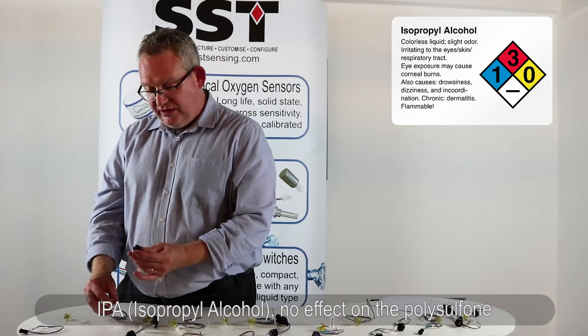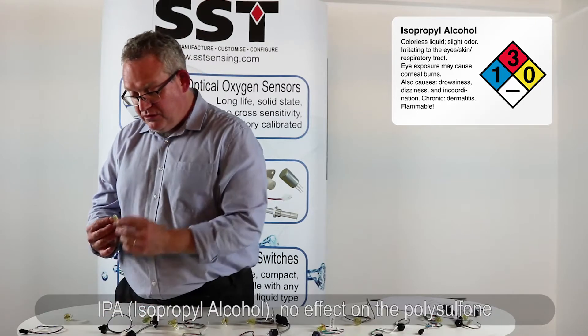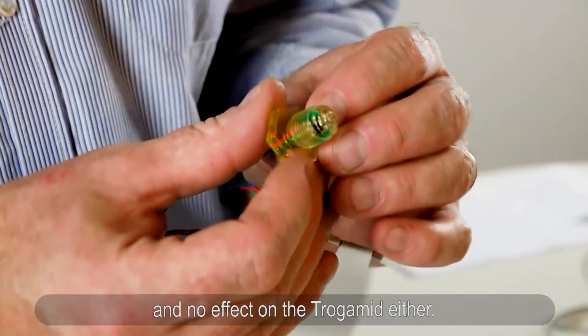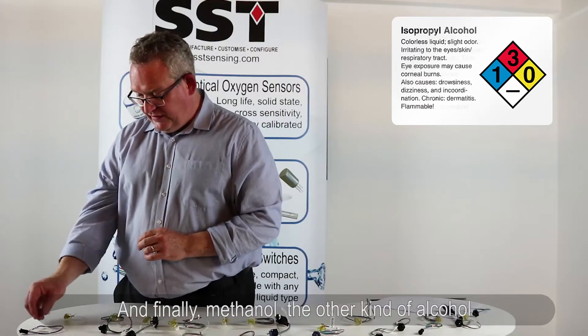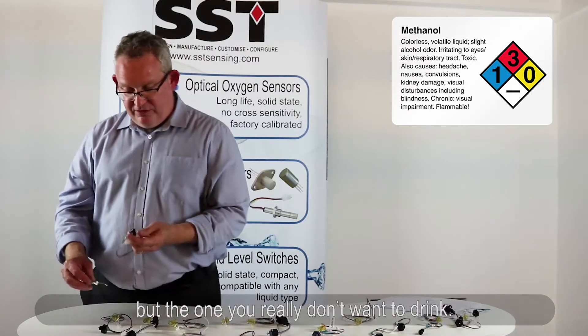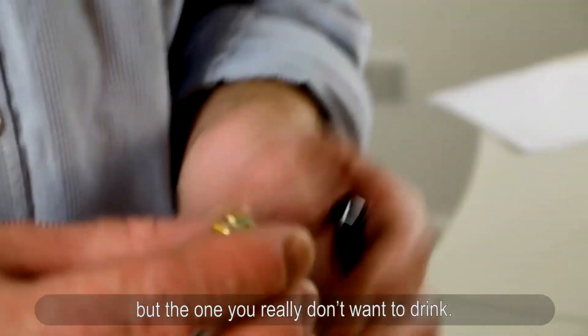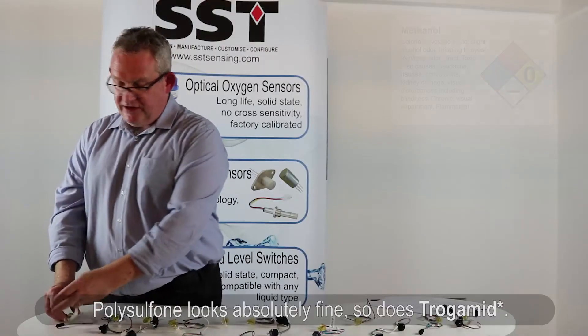IPA — isopropyl alcohol — no effect on the polysulfone and no effect on the trogamid either. And finally, methanol — the other kind of alcohol, the one you really don't want to drink. The polysulfone looks absolutely fine, and so does the trogamid with methanol.